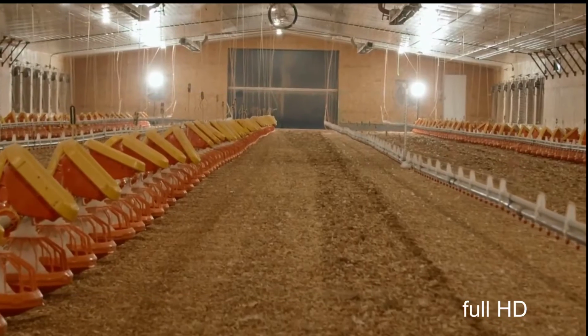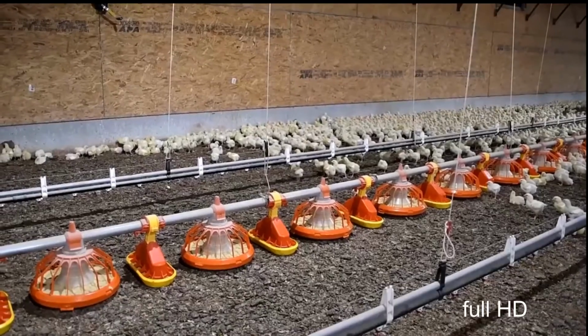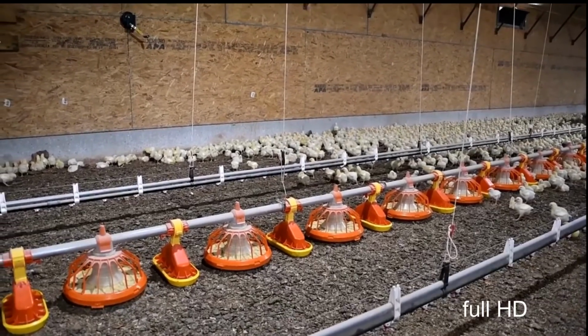Now, radiant heat systems are a little bit different. It's sort of like sunshine. On a sunny day, it's cold outside, the sun comes out, you can feel that heat, which heats both the floor and the birds directly. Because we're heating the floor, we're going to get some drying of that litter, so we minimize the production of ammonia and we have nice dry litter for those birds to walk on.